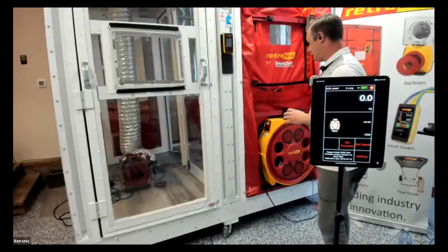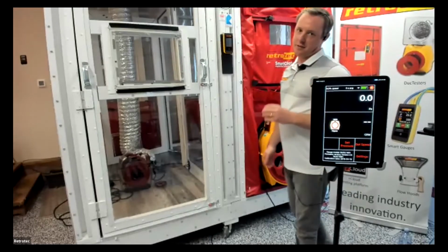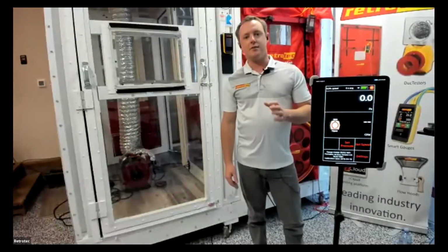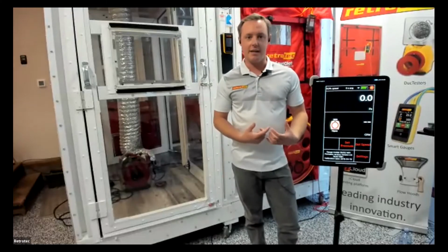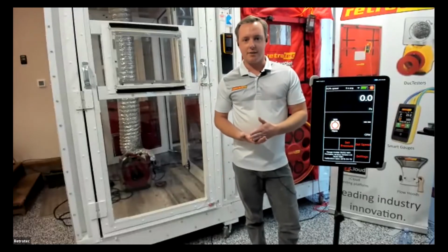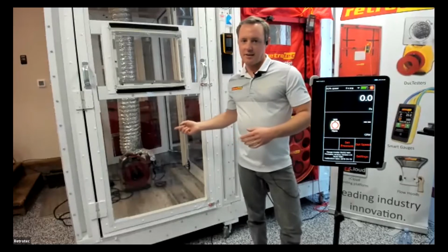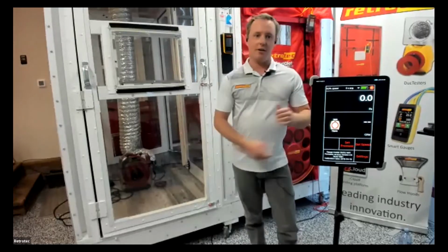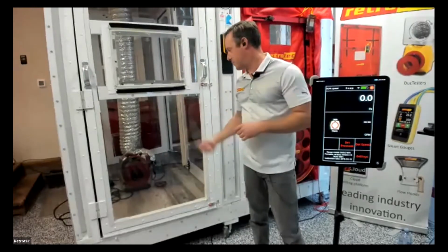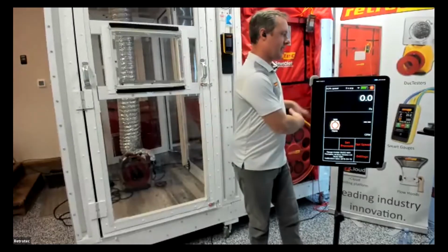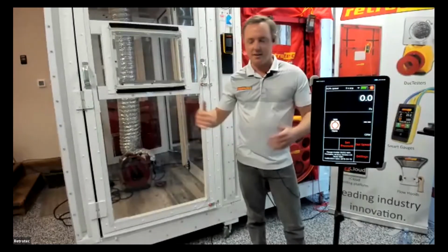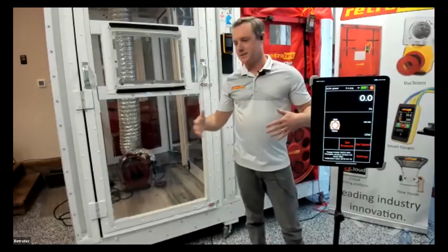So what I usually want to do is go ahead and get the blower door running first. The reason I want to do that is because it's a more powerful fan. Once I get that up and running to 25, then the duct tester fan isn't going to be overpowered by the blower door. Sometimes if you run that fan first, the blower door can overpower it, and sometimes it can just take a little while for the two of them to reach that equilibrium.